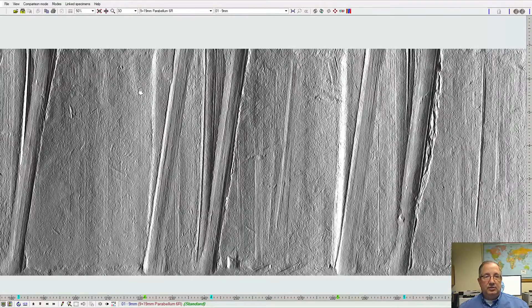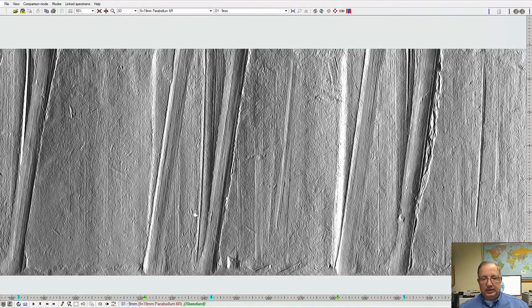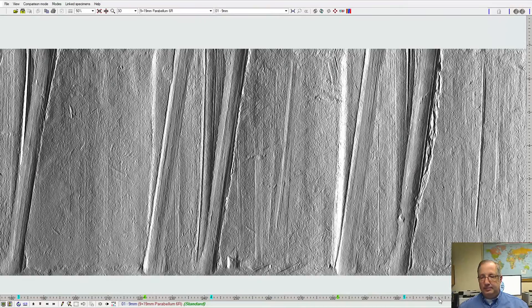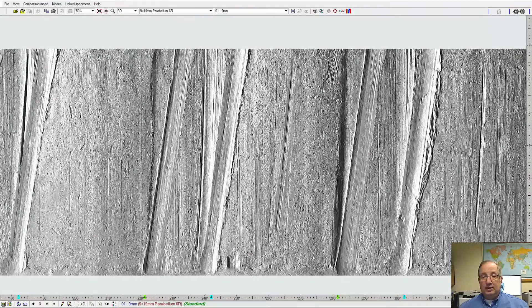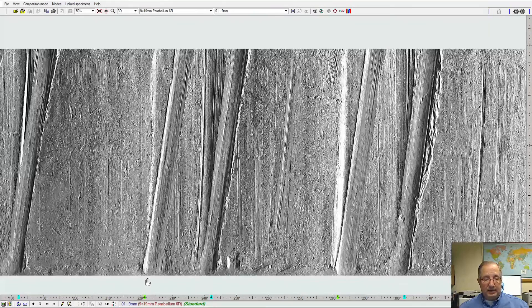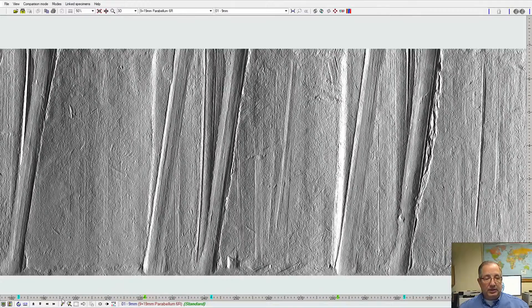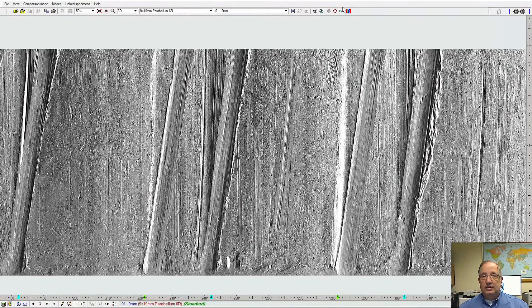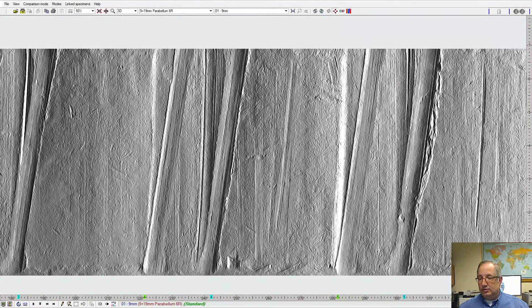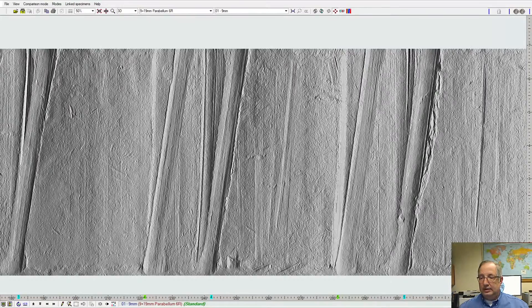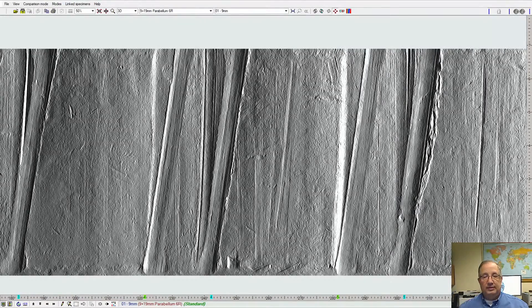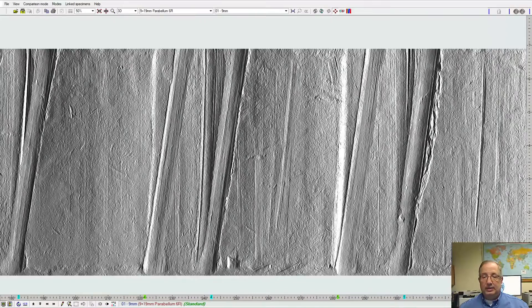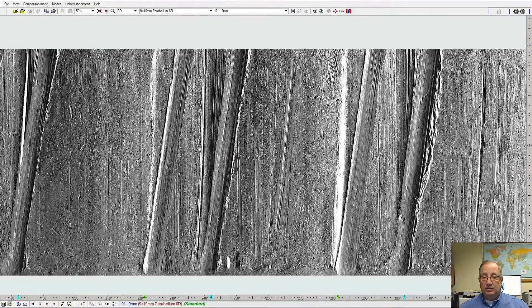And then we can use this to manipulate the sample. So we can change our lighting orientation. We can see the lighting from the right or the left side. We can also come in, change our brightness, contrast, and use our lighting controls to make the light more on-axis or more oblique for the sample that we're looking at. We can lock that into position using our lock controls.